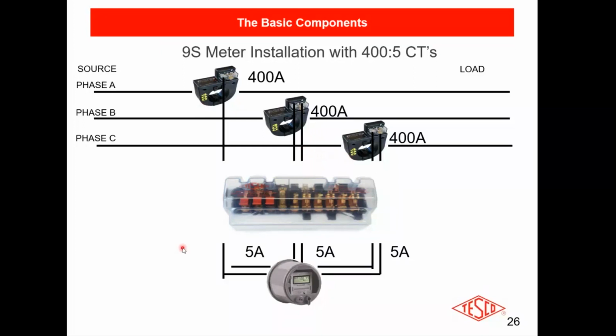And for those of you that were on the call last week, the reason that we go 400 to 5 is because the very first polyphase meter that was designed by Westinghouse in about 1898 was a dual stator meter, and it was most accurate at 5 amps. And so all of the instrument transformers were made to go to 5 amps, and we never got away from that practice. Do we need to do it today? We don't need to do it today, but we've just always done it that way. Once upon a time, those polyphase meters' sweet spot was 5 amps. When you test polyphase meters, typically full load is still 5 amps. That's what's considered full load.